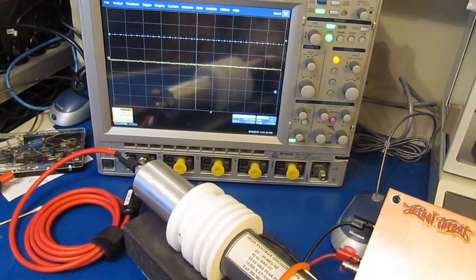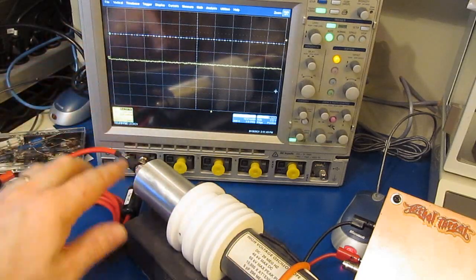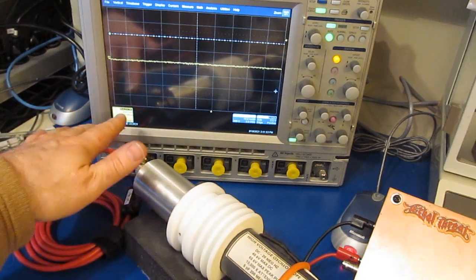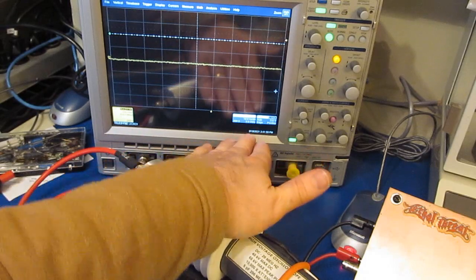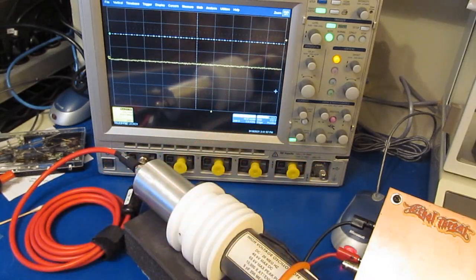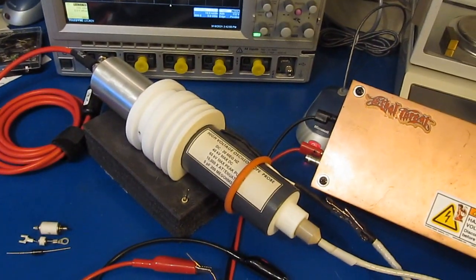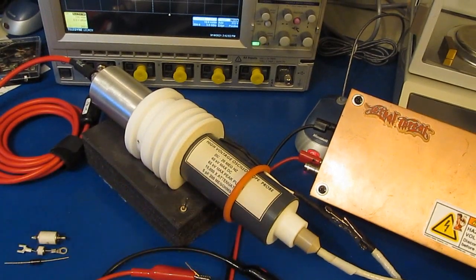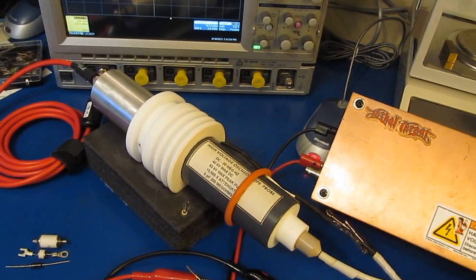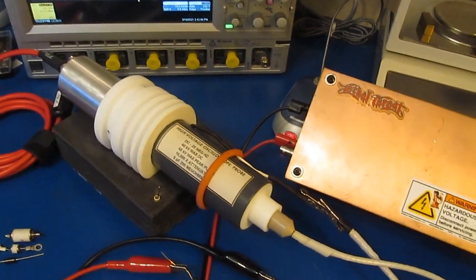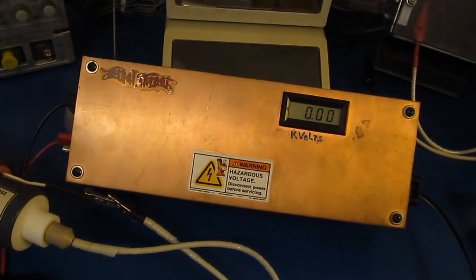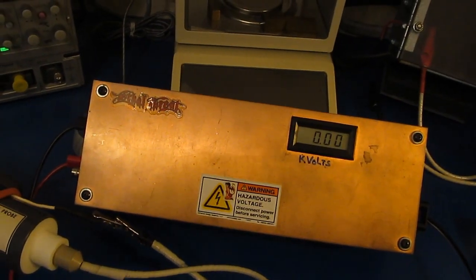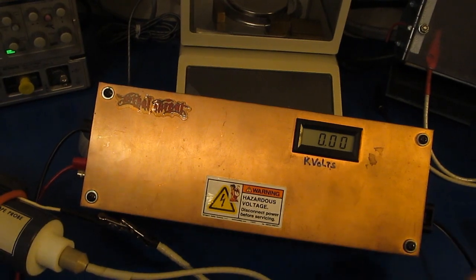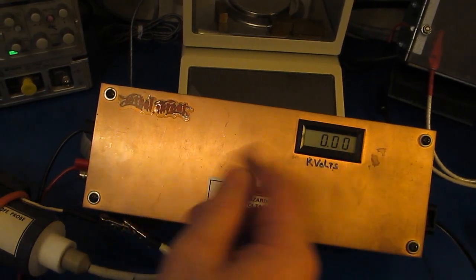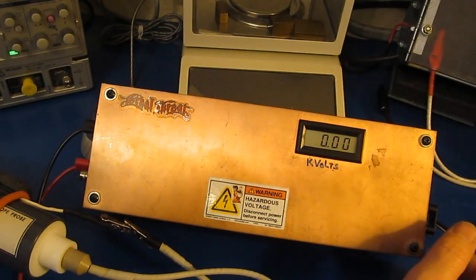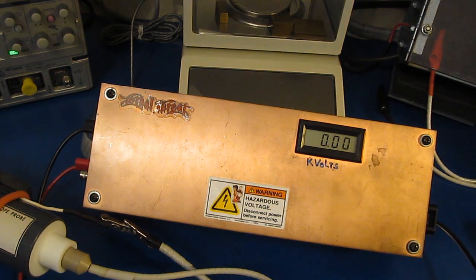We're going to run a quick experiment. Off to my left is our oscilloscope, currently set for 100 volts per division and 10 nanoseconds per division, attached to our high voltage probe. This probe is rated for DC to 20 megahertz and can handle up to 65,000 volts peak. Off to the right is our transient generator, which can put out both a pulse and a DC voltage. We're going to use the DC voltage mode.